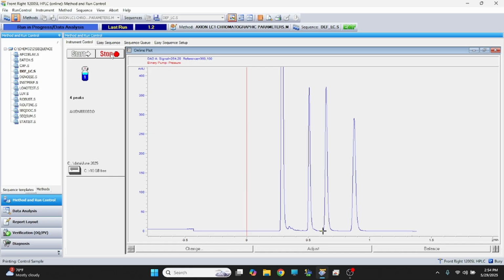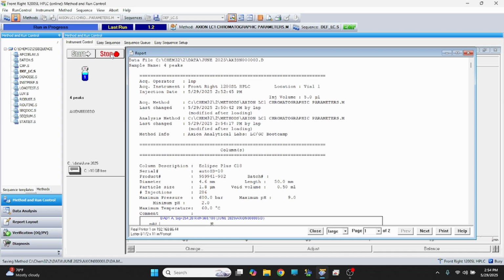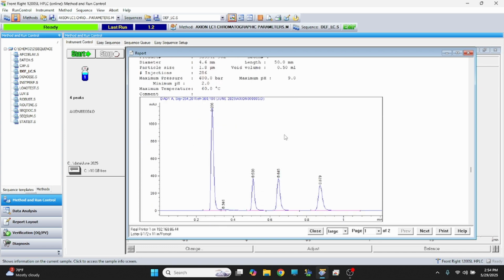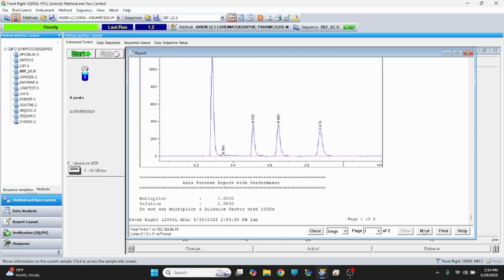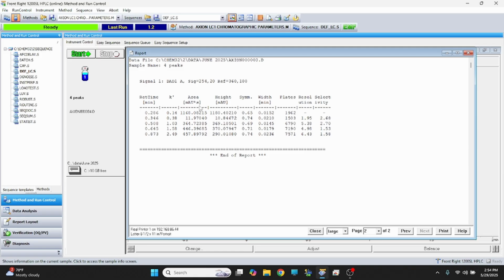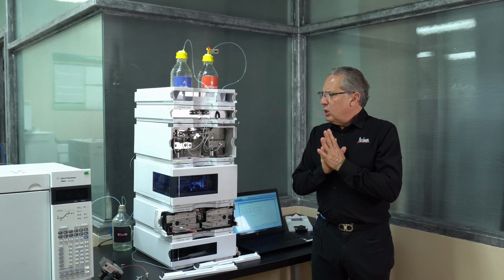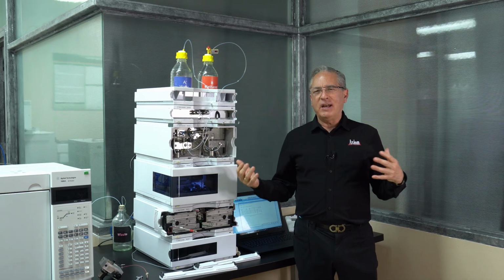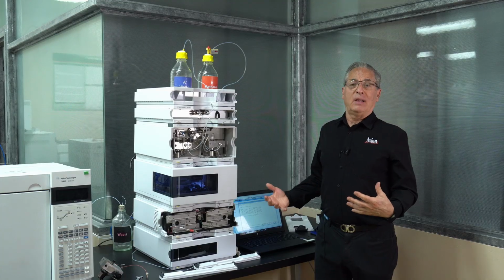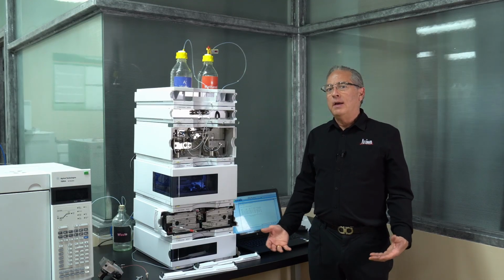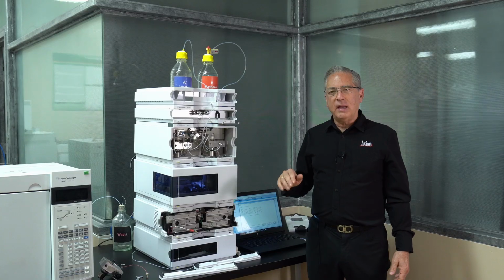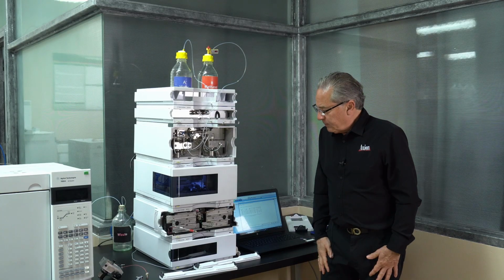So in this case, it stops acquiring, analyzes the data, finds the baselines, and then gives us a printout. And the printout, again, shows us the chromatogram, and on the second page, tells us a little extra information about how skinny are the peaks and how good is the separation. In this case, I'm running about 7,500 theoretical plates. It's a nice number of plates. Okay, so I just took you through how we were to make an injection on HPLC and how to just nominally analyze the data, look at the chromatogram. What are we looking for? We're looking for a nice flat baseline, and we're looking for symmetrical peaks.